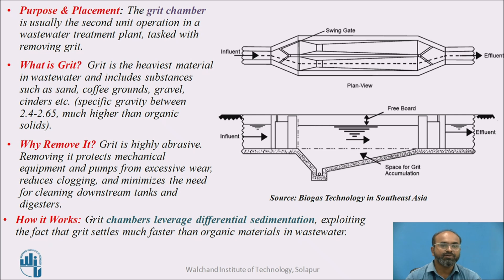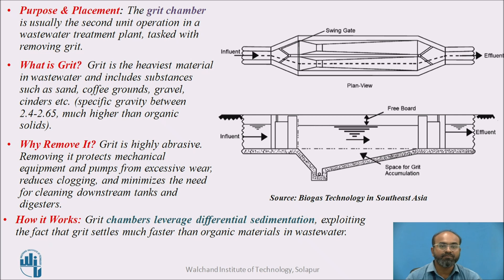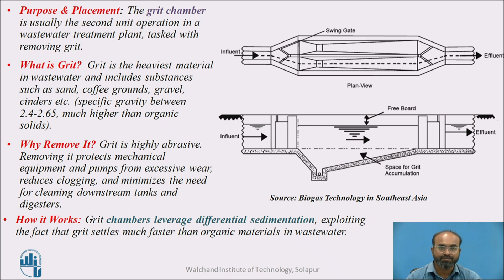Now why do we need to remove grit? Grit is heavily abrasive, which can damage mechanical equipment and pumps from excessive wear. Removing grit also reduces clogging and minimizes the need for cleaning downstream tanks, which are provided in biological treatment units and digesters in secondary or tertiary treatment units.